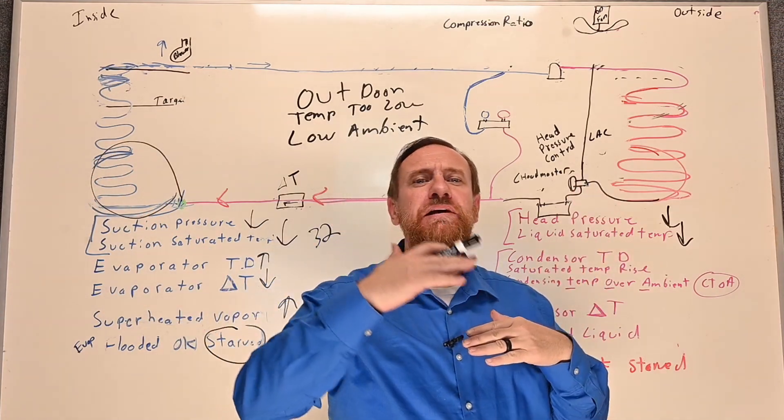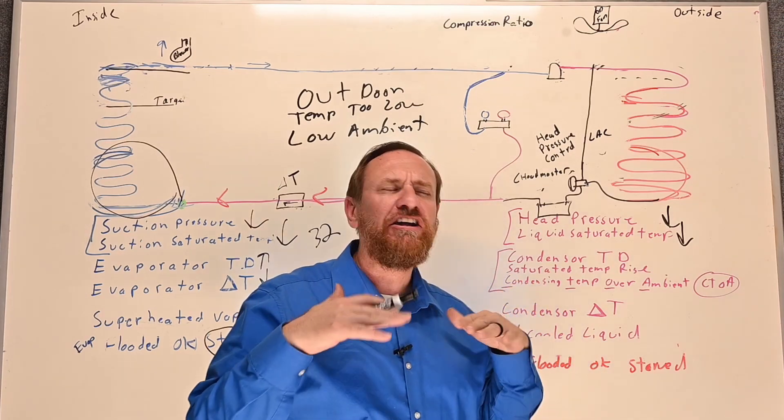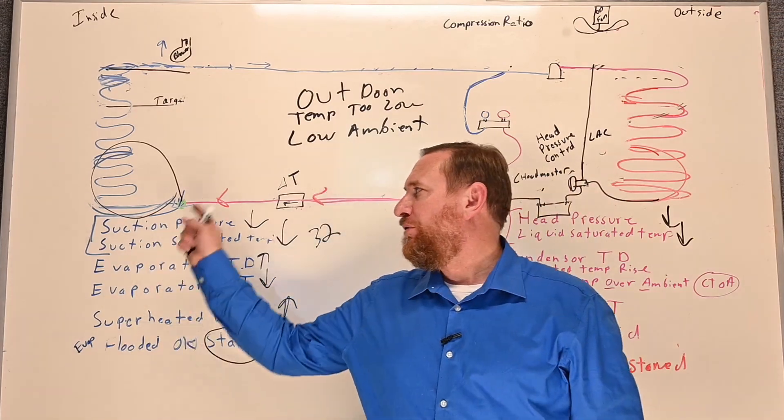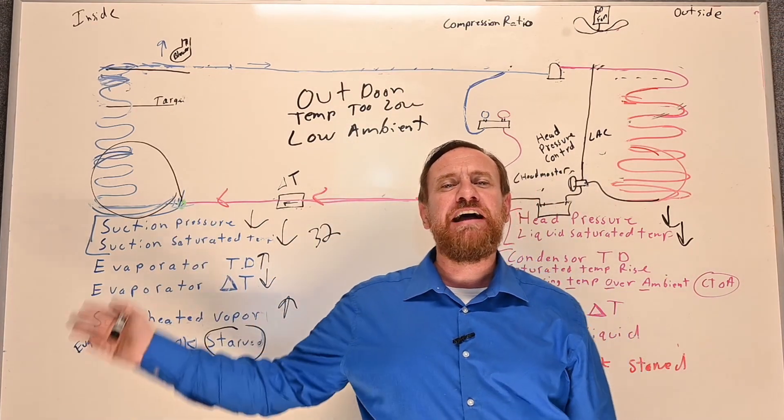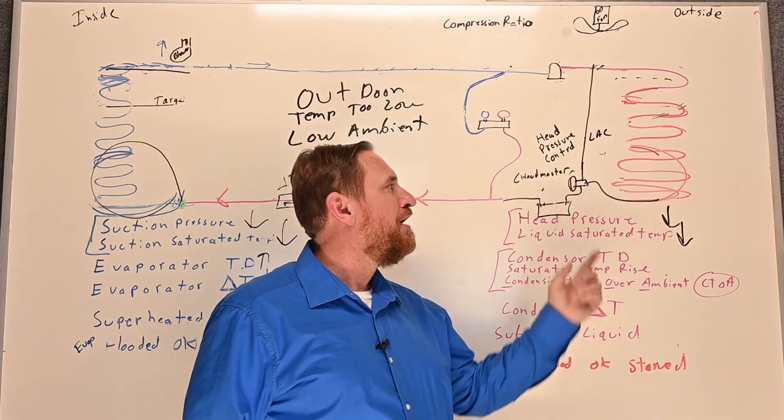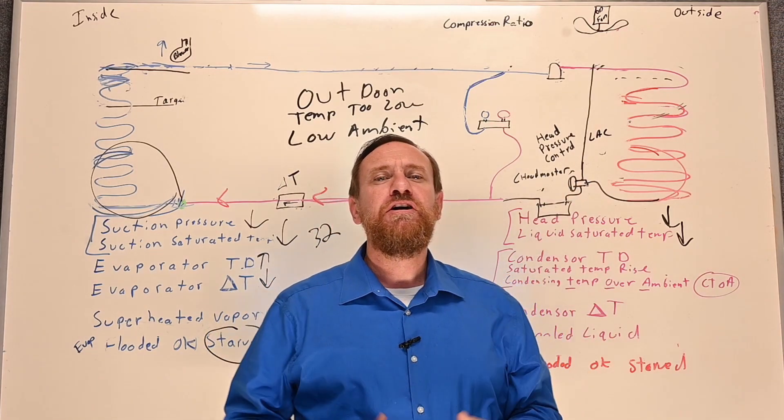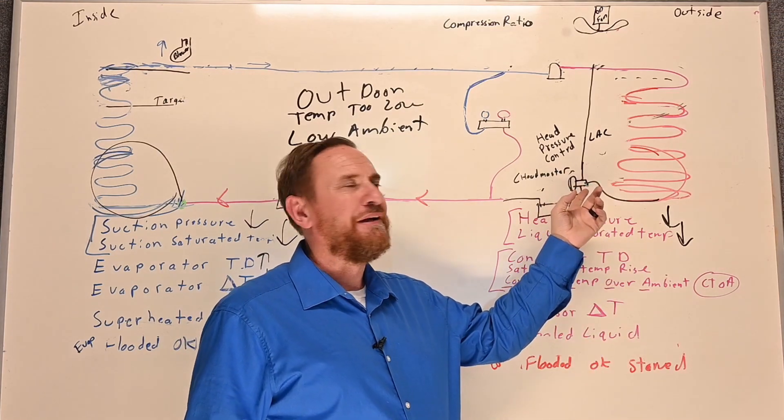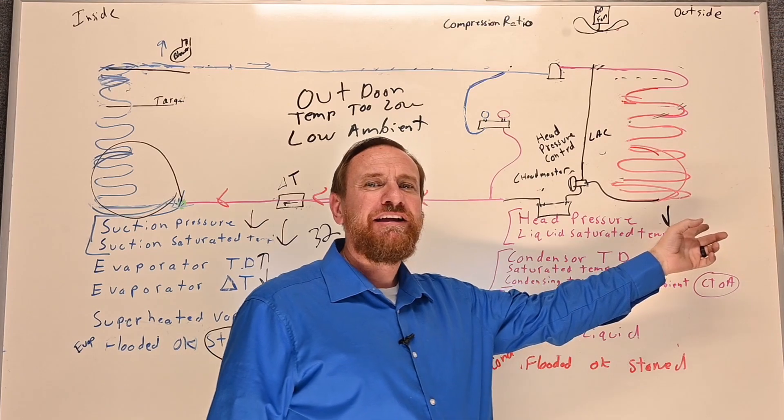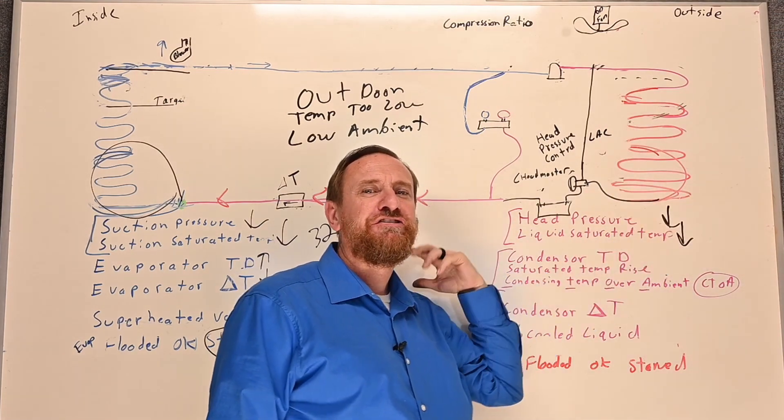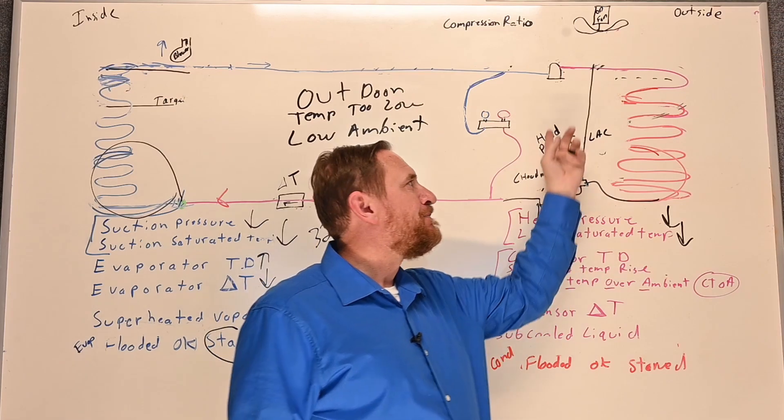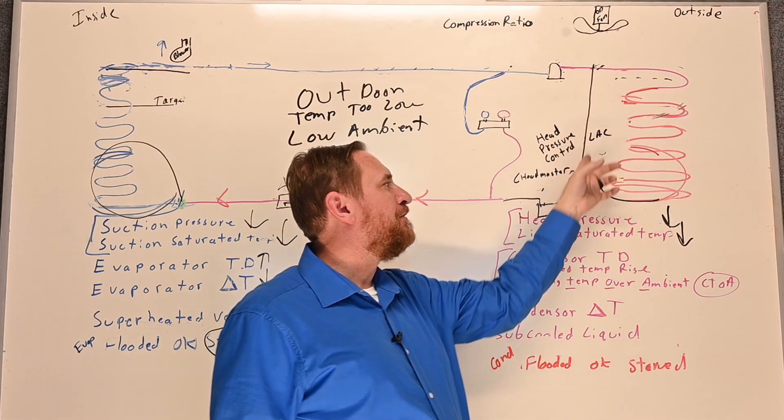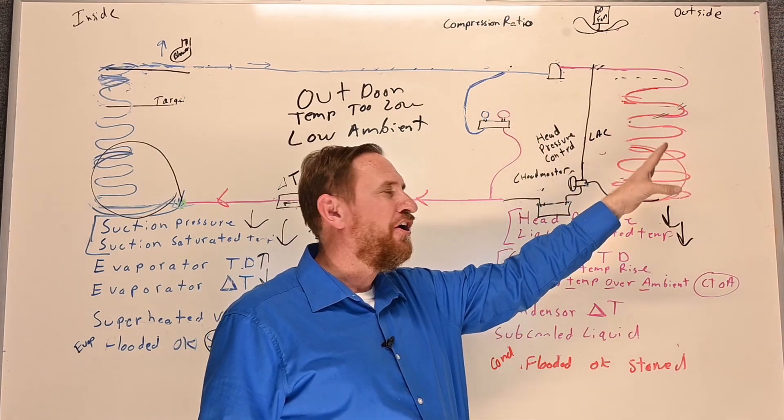Now what's cool about this is it can open and close in stages. Very smooth operation. So we can maintain the right amount of pressure going into our metering device and our vapor to cool. So it works really smooth. But they do have the three pipes and it does confuse a lot of people. When you see these go bad, what they'll typically do in low ambient conditions, they simply won't open. And you end up with low ambient conditions, a low head pressure, and all the other situations that happen. So if it is working correctly, then as the temperature outside starts to drop, you end up with this bypassing the fans and bypass the condensing unit altogether.